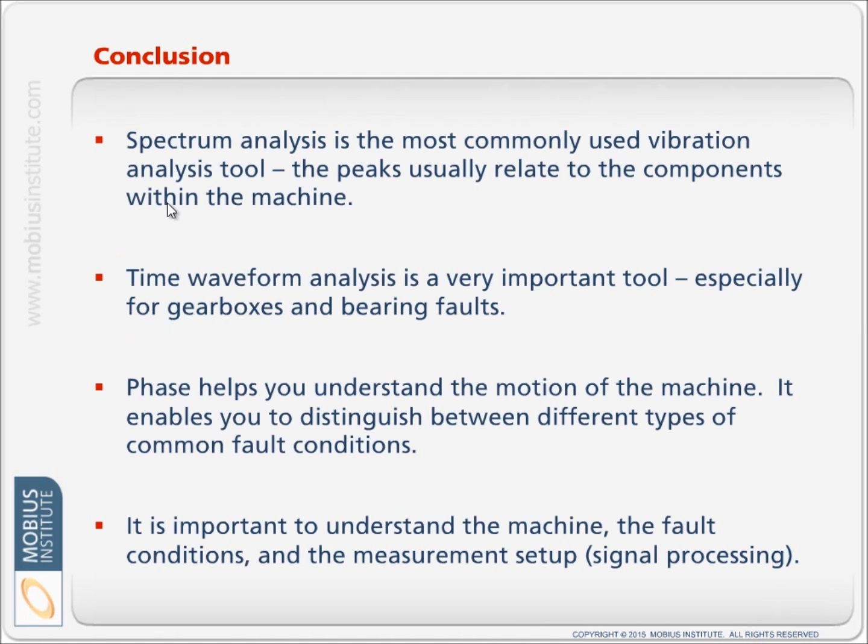In conclusion, spectrum analysis is the most commonly used vibration analysis tool. The peaks usually relate to the components within the machine. It helps us diagnose faults and determine if there is a problem to look at more closely. The time waveform is used to create the spectrum but is also a very useful analysis tool and should be used particularly on gearboxes and rolling element bearings. Phase analysis helps us understand the motion of the machine. It can help distinguish between unbalance and misalignment and eccentricity and bent shaft and other sorts of faults.